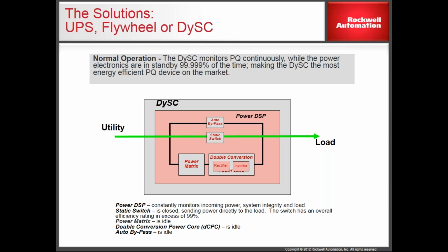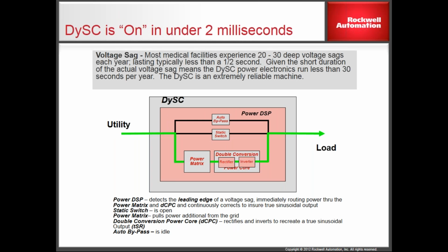A DySC, it's a series device. The power flows from the utility to the load through a static switch in the DISC. So it's in series with the load. And it's monitoring all the time, monitors that waveform. When it sees that voltage drop or the 0 crossing point of the waveform shift, then it turns on and becomes a power supply. And when it does that, the power now flows from the utility down through something we call a power matrix, then a double conversion power core, goes AC to DC and back to AC, and I actually rebuild the sine wave, true sine wave, just like it looked before the event started to happen, and that's what comes out and powers my load.